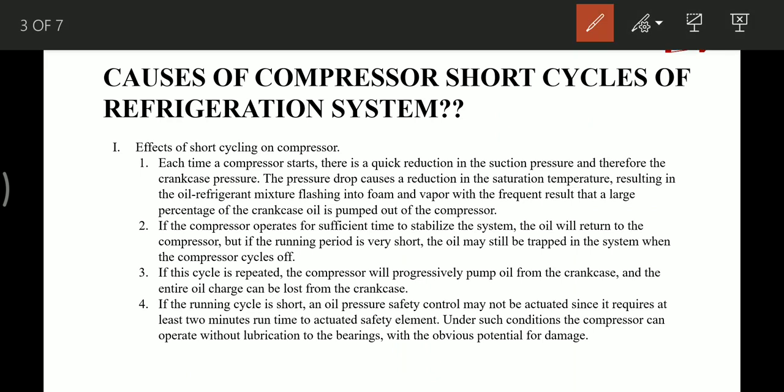Each time the compressor starts, there is a quick reduction in suction pressure and therefore the crankcase pressure, as the compressor takes suction from the crankcase. The pressure drop causes a reduction in saturation temperature, resulting in oil refrigerant mixture flashing off into foam and vapor with the frequent result that a large percentage of crankcase oil is pumped out of the compressor.